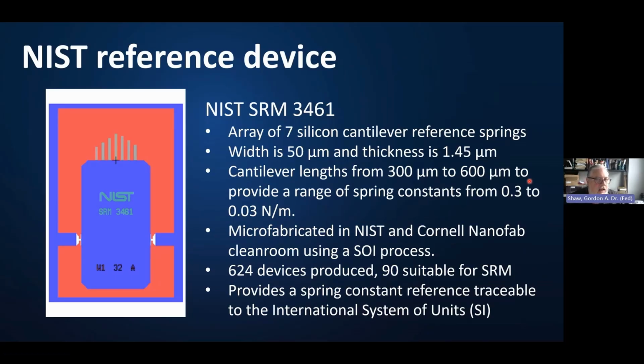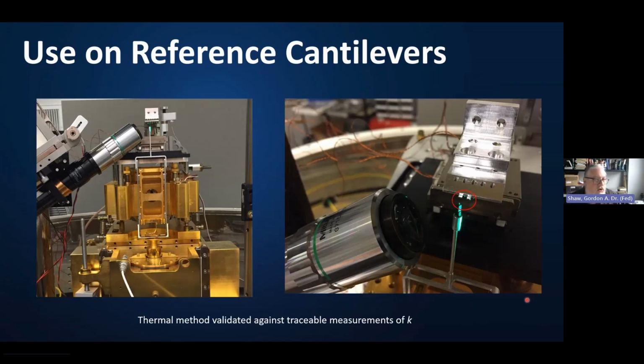We have developed a standard reference material, SRM 3461, that is an array of 7 of these cantilever reference springs that are shown here at the end. These small rectangles here are the cantilever reference springs. And they're microfabricated by NIST in the Cornell NanoFab clean room. We have about 90 of these that have been produced, and they provide a spring constant reference that's traceable to the International System of Units. And we get our traceability using the electrostatic force balance.